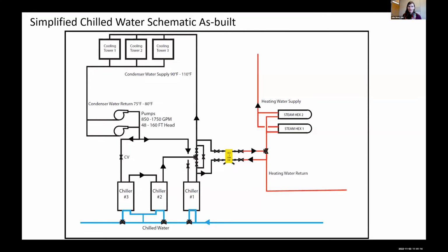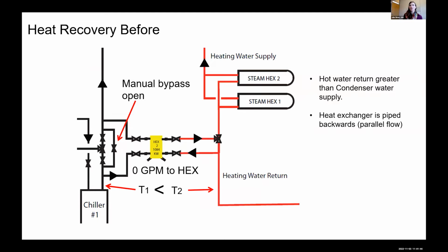And when we looked at the heating water schematic, I mentioned before that we do have a plate and frame heat exchanger that was supposed to be used for heat recovery from the chilled water system condenser side to the heating system in the building. That's this heat exchanger here. There were 2 reasons why this wasn't working. One is that there was a manual bypass that was open that was basically allowing flow to be rejected around the hex, and so there wasn't actually any flow going through it.